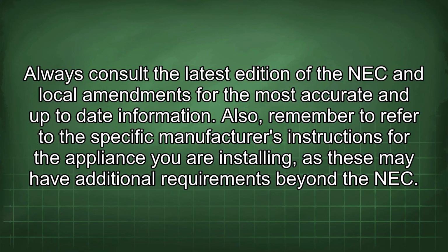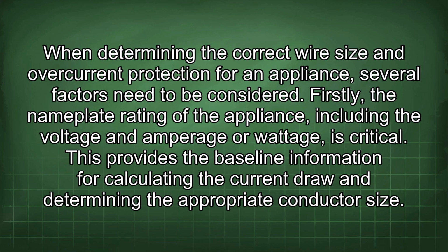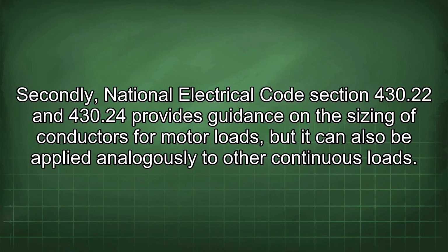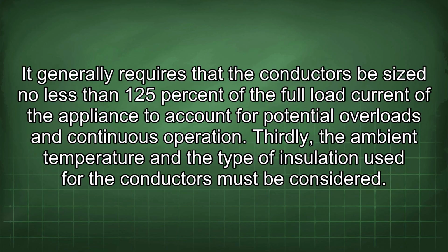When determining the correct wire size and overcurrent protection for an appliance, several factors need to be considered. Firstly, the nameplate rating of the appliance, including the voltage and amperage or wattage, is critical. This provides the baseline information for calculating the current draw and determining the appropriate conductor size. Secondly, National Electrical Code Sections 430.22 and 430.24 provide guidance on the sizing of conductors for motor loads, but can also be applied analogously to other continuous loads. It generally requires that the conductors be sized no less than 125% of the full load current of the appliance to account for potential overloads and continuous operation.